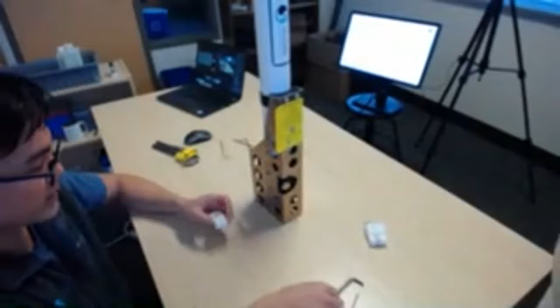Now recall that these electrodes are not meant to dry out. So while it's in the HydroCAT EP right now, it's actively drying out. We have some time. It's wet. It's going to take a while for it to completely dry. But anytime you are leaving the HydroCAT EP out of water, say for more than an hour or so, I would recommend reinstalling your pH sensor back into the soaker block and making sure that you have KCl solution in the soaker block. But for now, we've got time. So this is looking pretty good.